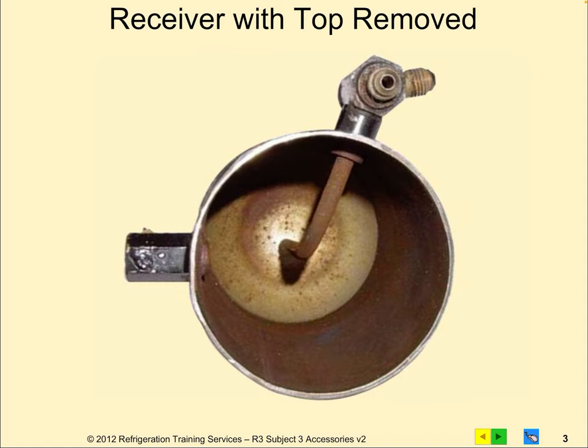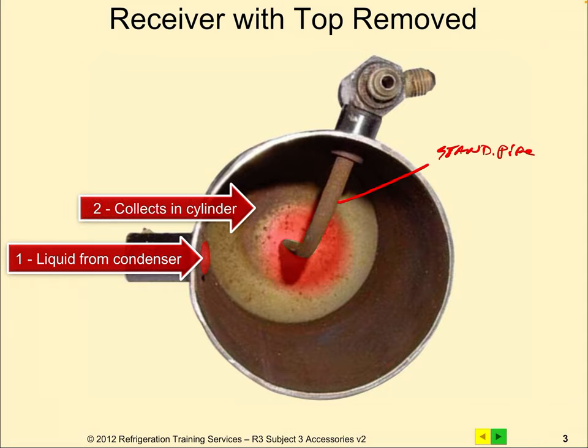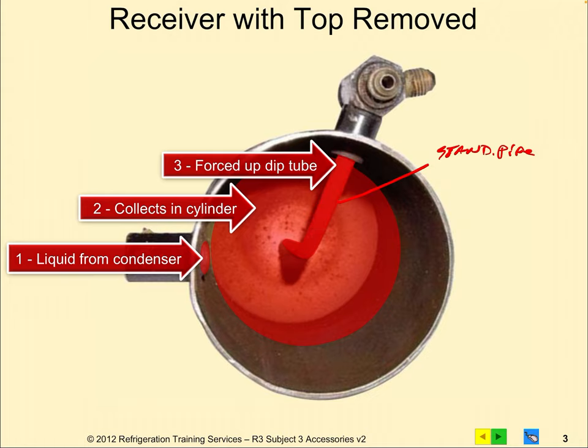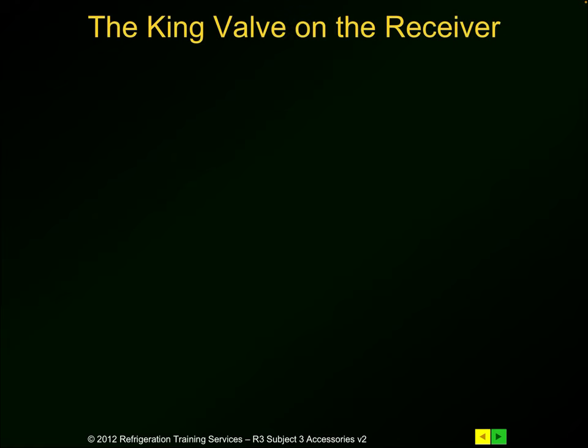Here's a cutaway of a receiver — you can see that little standpipe, also called a dip tube. Liquid comes in and falls into the cylinder, collecting there whether it's oil or liquid refrigerant. Then it gets forced up the dip tube and comes out through the King valve. This is actually the service valve that allows access to the system. It's a pretty nice little system.